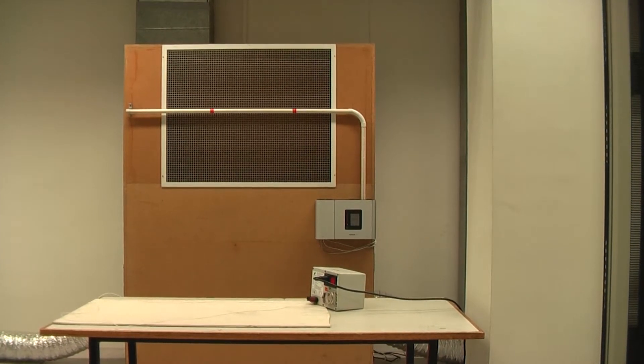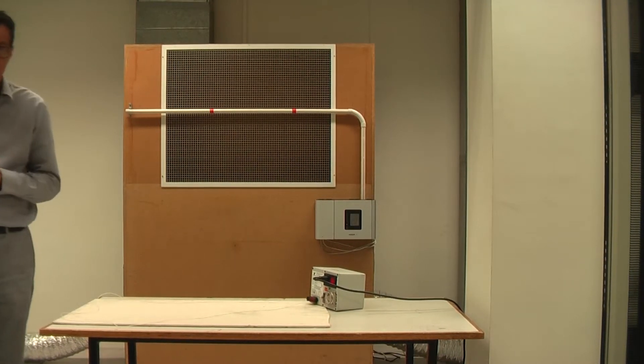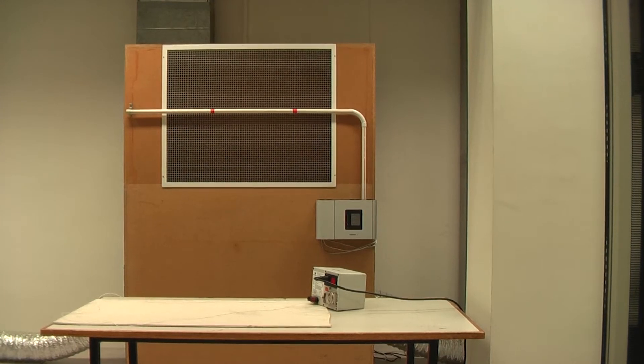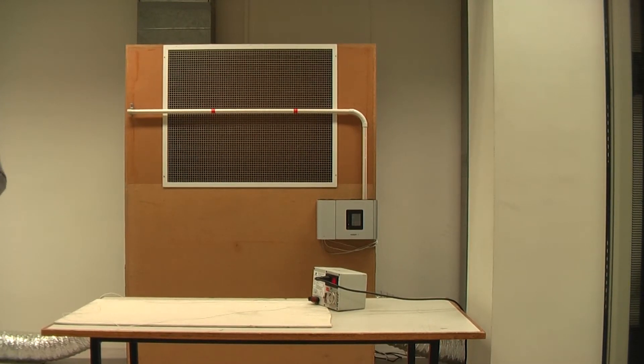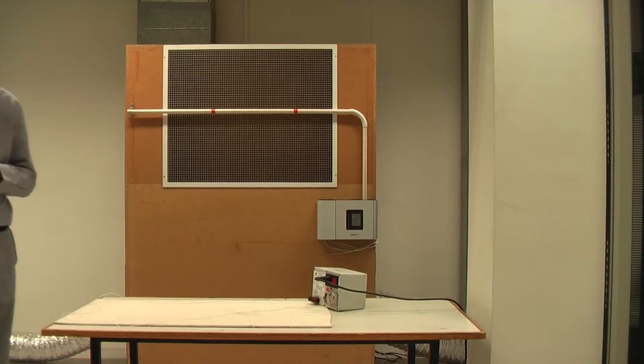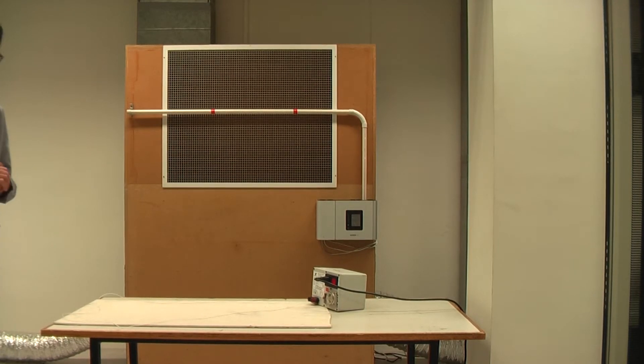The standard specifies an energization period of 180 seconds. However, for the purpose of this test, we're going to be generating lesser amounts of smoke, so we have kept the energization period to 30 seconds.